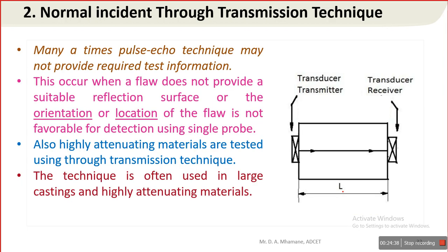So this is all about the through transmission technique. It is very similar to the pulse echo technique. The principle is exactly the same, the only difference is that we are using two different probes on either side of the component.